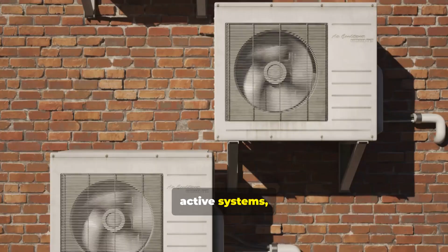The granite itself acts as a massive thermal battery. Its volume and density absorb vast amounts of heat with negligible temperature increase. That buffer smooths short-term heat fluctuations from the servers. If there's a sudden computational spike, the surrounding rock passively absorbs excess heat, preventing rapid temperature rise in the data hall. Passive cooling reduces reliance on active systems, creating a more stable, predictable environment with less energy use.